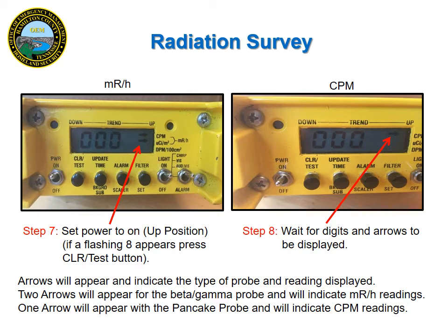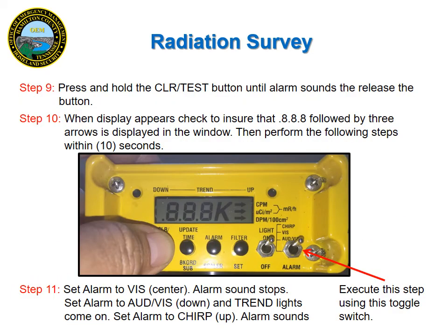If for some reason there is a flashing 8 on the screen, press the CLR/test button. Then wait for digits and arrows to be displayed. The arrows will indicate the type of probe and reading displayed. 2 arrows are going to be used for beta and gamma probe, and 1 for the pancake probe, which is what you will be using in most cases. When using the pancake probe, the reading will always be in counts per minute or CPM. To continue, press and hold the CLR/test button until the alarm sounds.